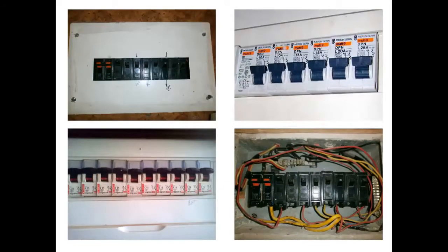In these pictures you can see the electrical boards usually found in our structures before upgrading them. Be sure to always know the location of the electrical board of every structure to cut the electrical supply in case of an electrical accident or fire. They consist of several one-pole circuit breakers protecting the different secondary circuits of the installation, such as lights, sockets, air conditioner, water heater, etc. Let's now see the schematic of this kind of installations and how to improve them.